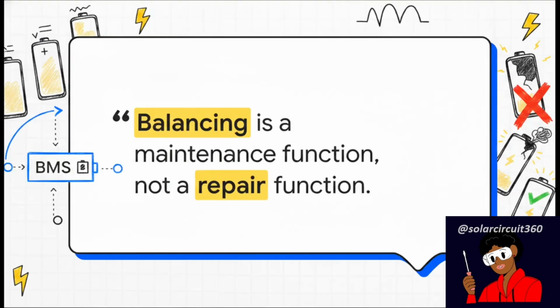Now, there's also this dangerous myth out there that turning on the balancing function will magically fix a badly damaged cell. Let's clear that up right now. It won't. Because no two lithium cells are perfectly identical. Slight voltage differences naturally happen between them over time. As the saying goes, balancing is a maintenance function, not a repair function. Passive balancing just gently equalizes those slight natural voltage differences over time to keep a healthy pack running smoothly. It is purely routine maintenance.